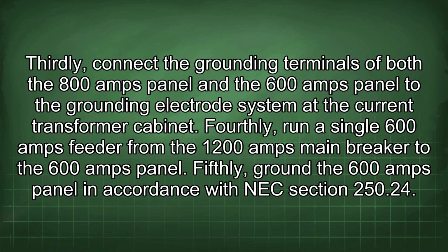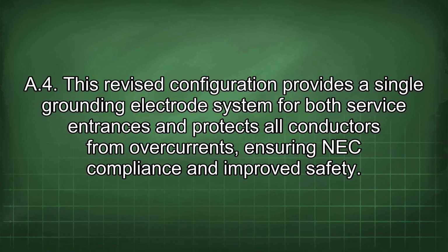Fifthly, ground the 600 amps panel in accordance with NEC Section 250.24 A4. This revised configuration provides a single grounding electrode system for both service entrances and protects all conductors from overcurrents, ensuring NEC compliance and improved safety.